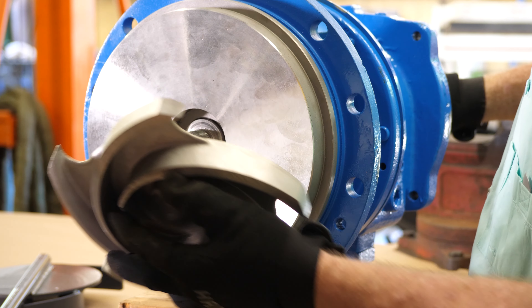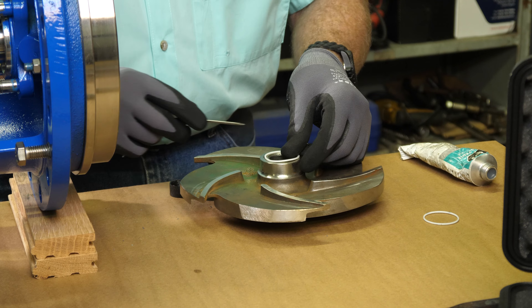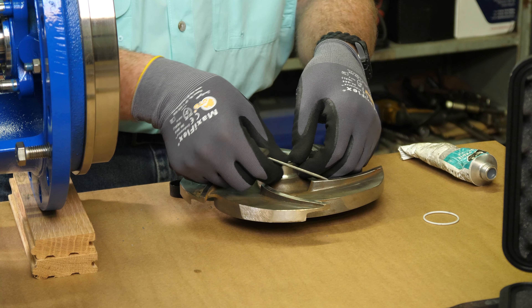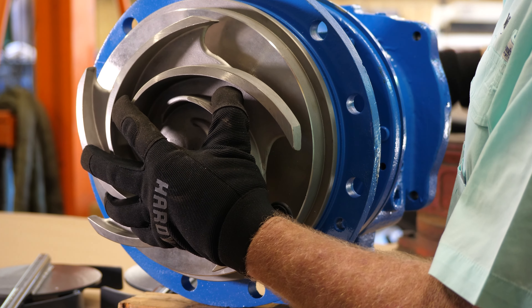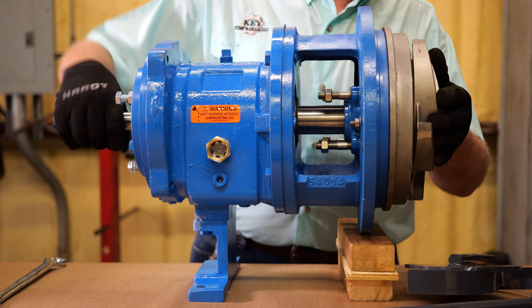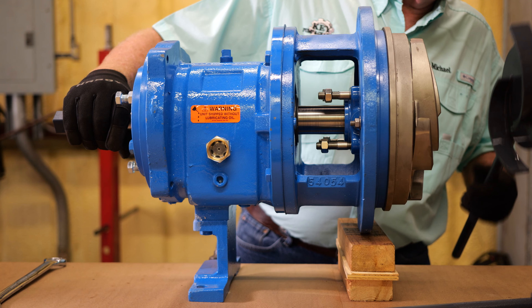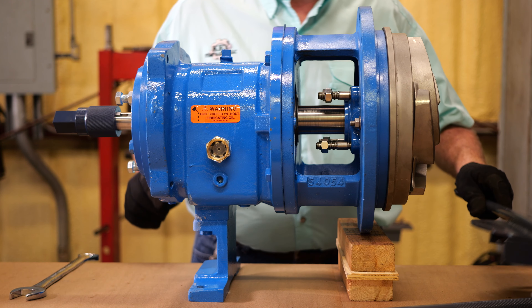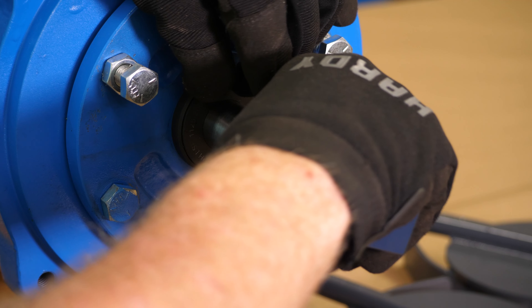Now you can continue with pump repairs. When your repairs are finished, simply reverse the process: install the impeller with a new impeller gasket onto the shaft and turn the input shaft socket forward until the impeller makes contact and is snug. Now use the impeller wrench to engage the vanes, using your combination wrench or crescent wrench to fully tighten it. Remove both wrenches, take off your input shaft socket and key — now you're all done.